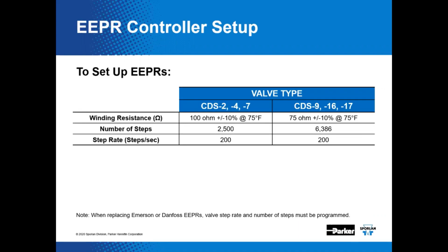If you're doing a CDS installation, whether it's new or replacement, be sure to program the valve resistance and program the number of steps and the step rate into the EMS or the standalone controller. We show the valve resistance right here. Some of them are set up as 100 ohms, plus or minus 10% at an ambient condition of 75 degrees. Others have 75 ohm motors.